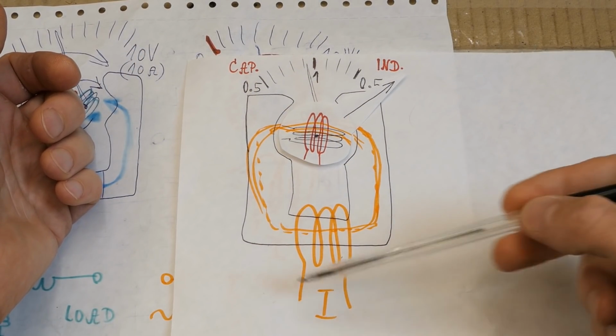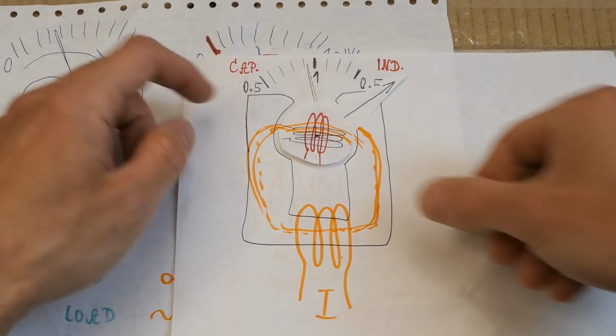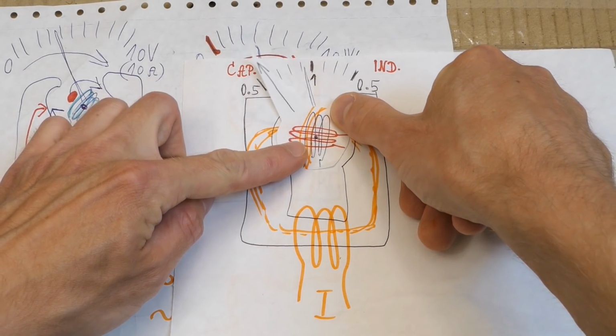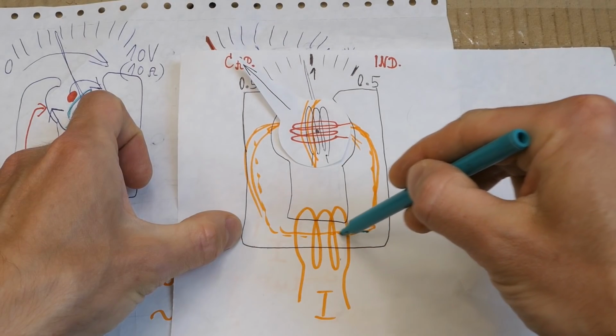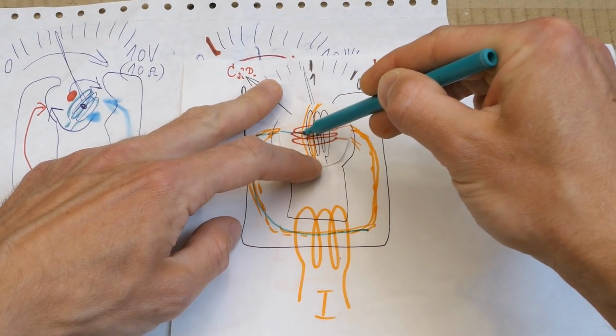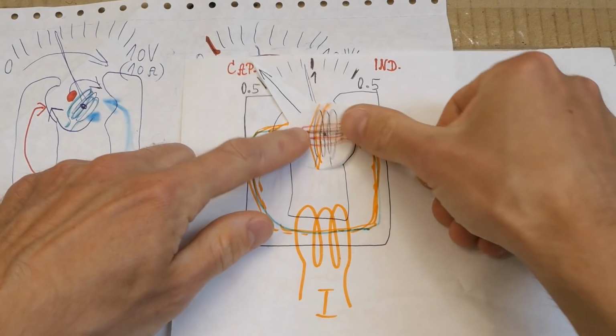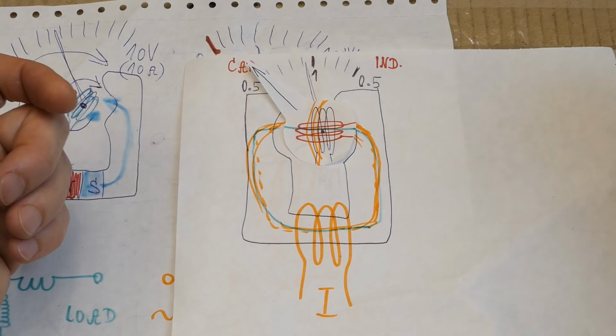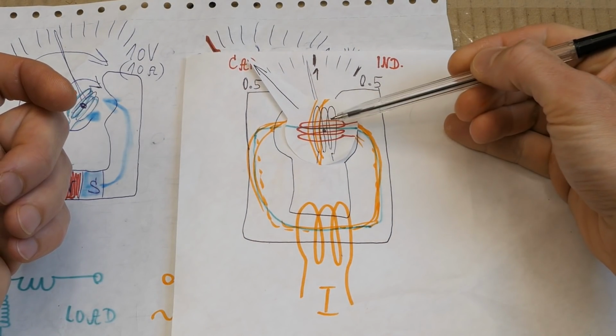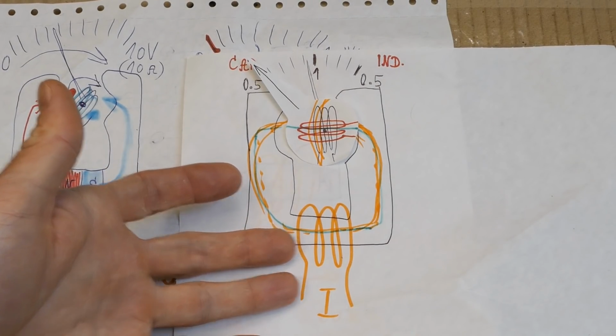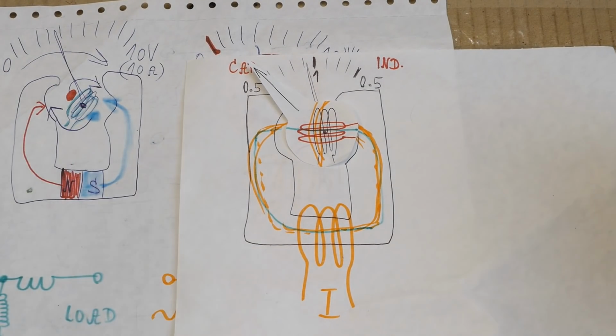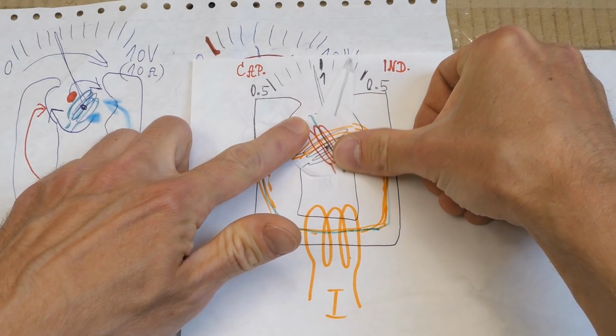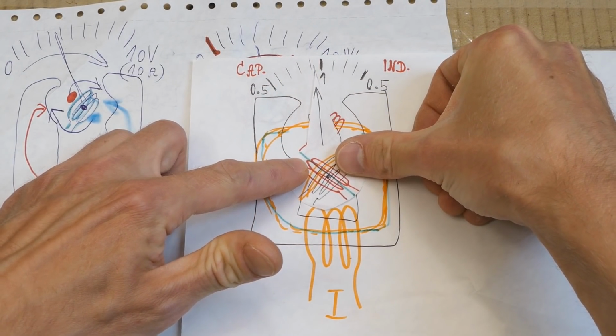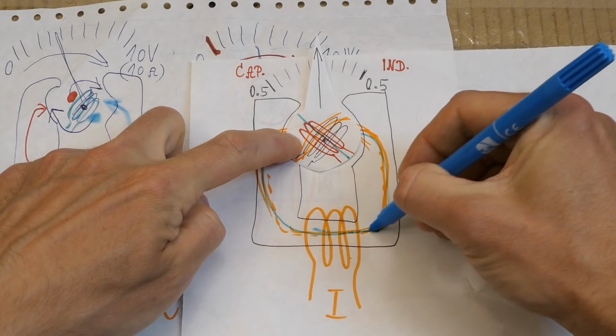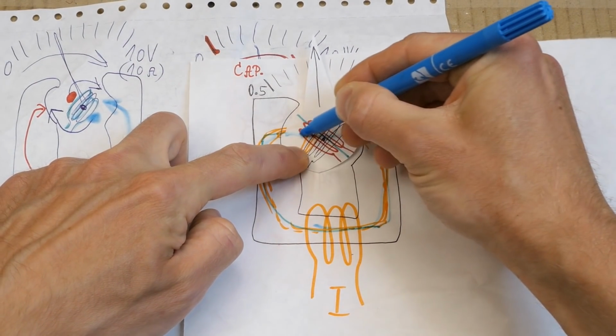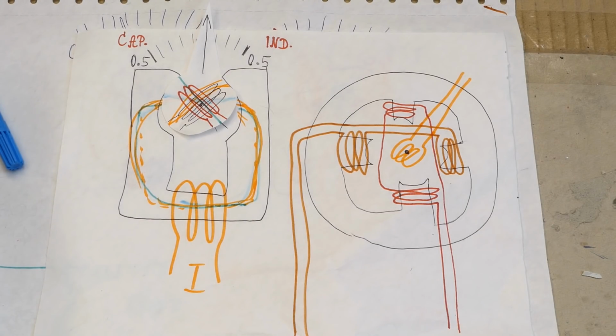If it's a capacitive load, the current is ahead here, and so the coil with the current ahead will align with this. The magnetic field goes like this, it goes through the coil which is ahead, and so it indicates a capacitive load. The black reference coil also has a current in it which is ahead. And if it's a resistive load with no phase shift, then one of the coils is ahead, one is behind, so they will balance and it will indicate a power factor of 1. Now both coils balance each other. So this is a simple explanation of how it works.